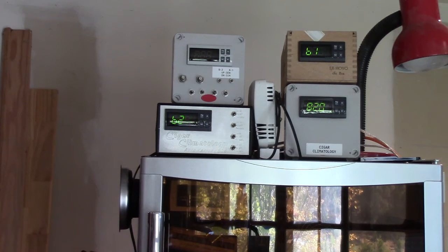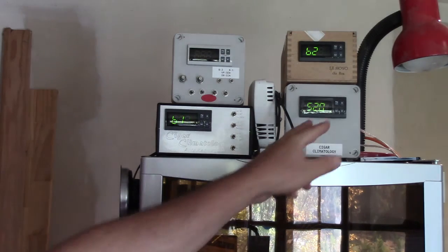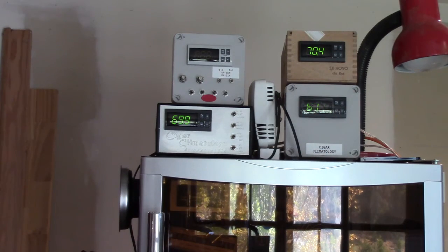Now, okay, so what's going to happen to this cooler if I open the door? You're probably thinking, well, it's 82, so maybe the temperature will go up a little bit, and because it's 50 RH, well, more than likely, it's a little drier out there. Well, that's really not the case, because remember, this is a discussion, or this is the realm of relative humidity, and in some ways, we have to look at absolute humidity, or how much water is actually in the atmosphere, or in the space, at any one given time.